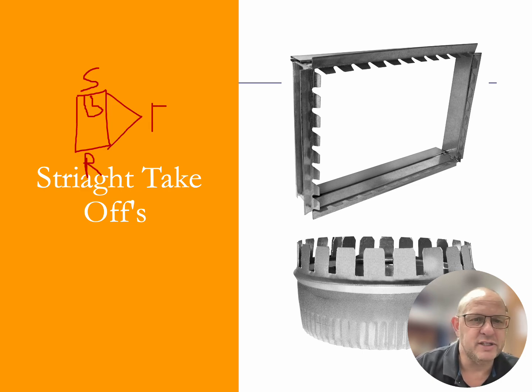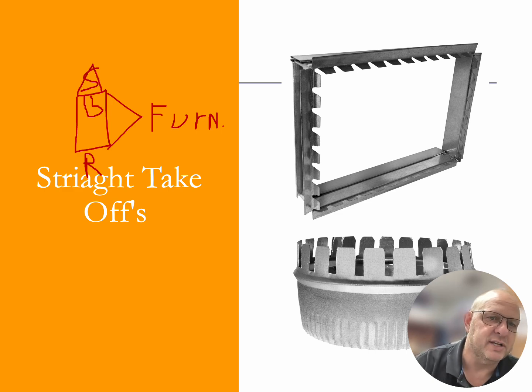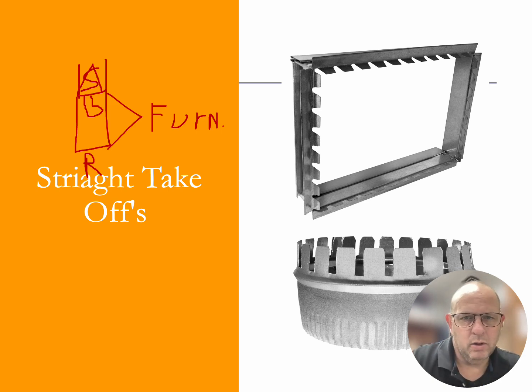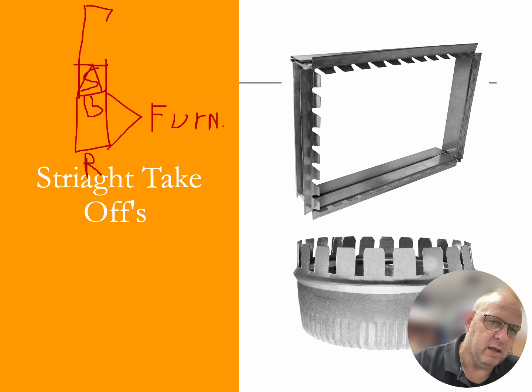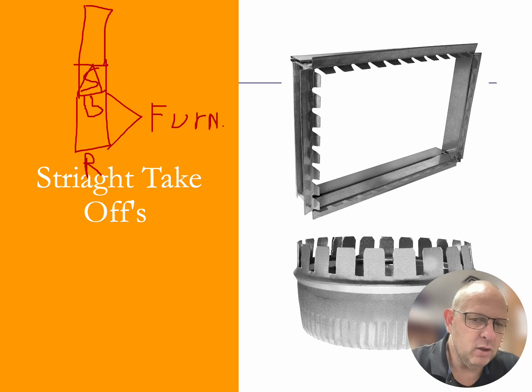Your air handler could be a furnace, or it could be a fan coil with an evaporator on the inside of it. Now, if it is a furnace, the next item that we're going to have on that furnace is some sort of boxed A coil on it. So the furnace is going to have that A coil on top of it with a fan coil that's going to sit there. Now off of that, we are going to run a plenum. That plenum is just an extension of the air that's coming off of the furnace. And off of that plenum, we are going to run what we call a takeoff.